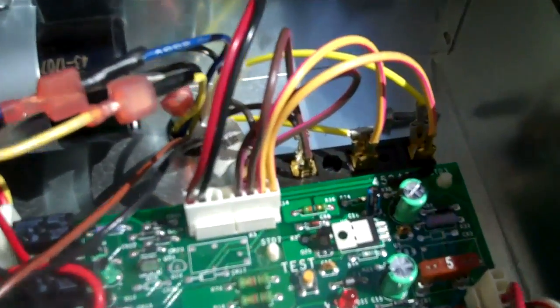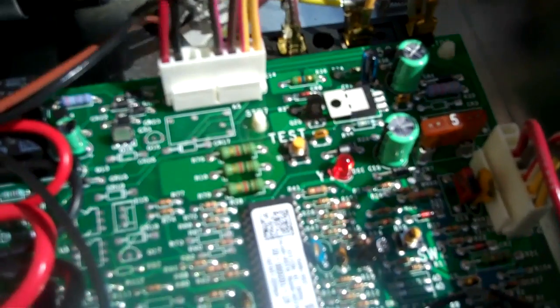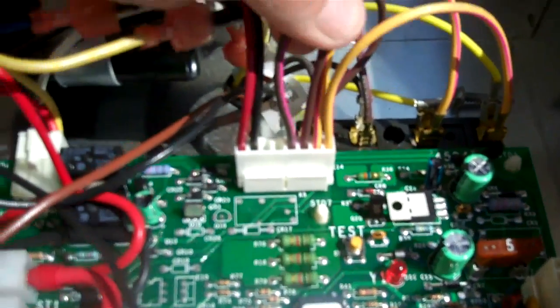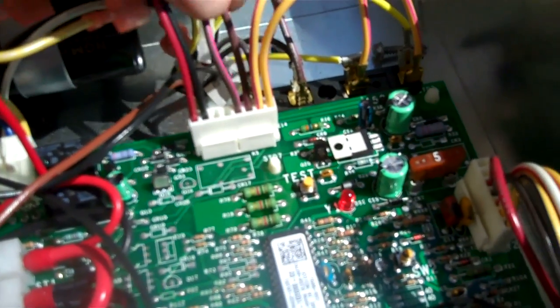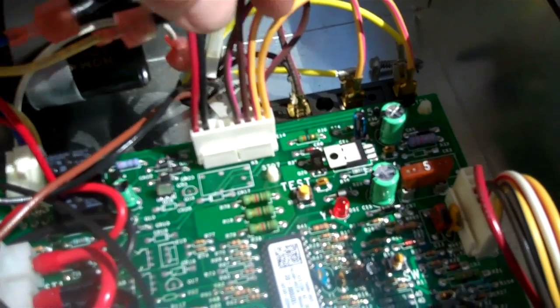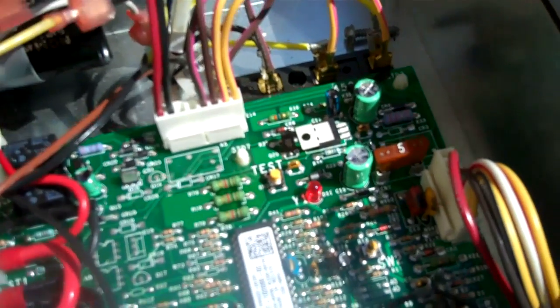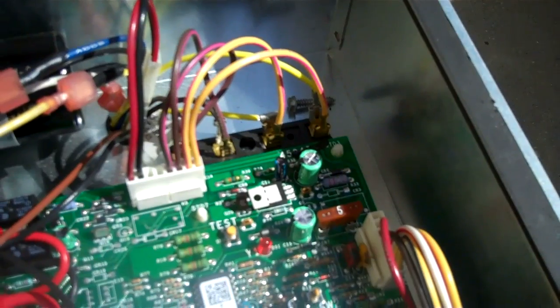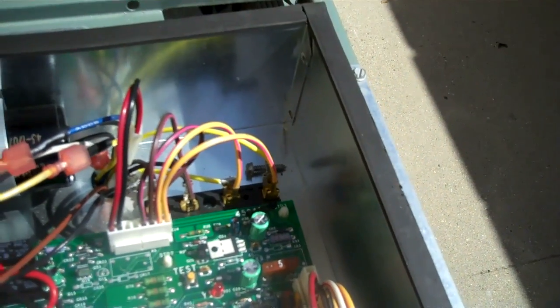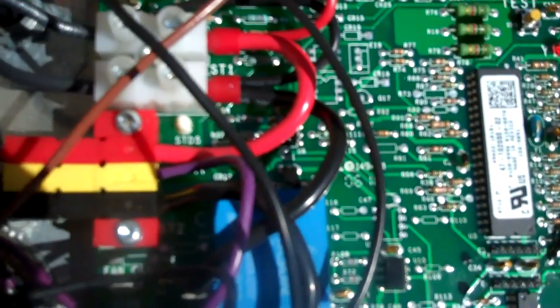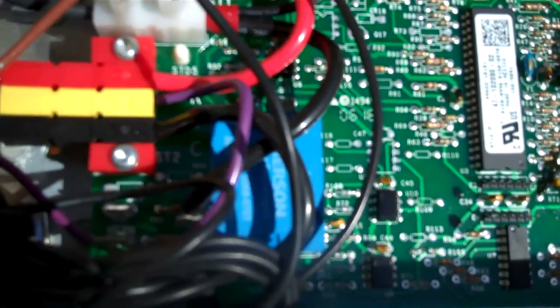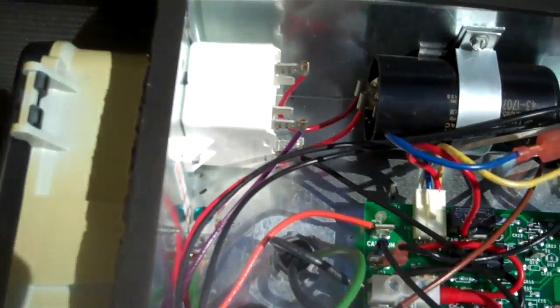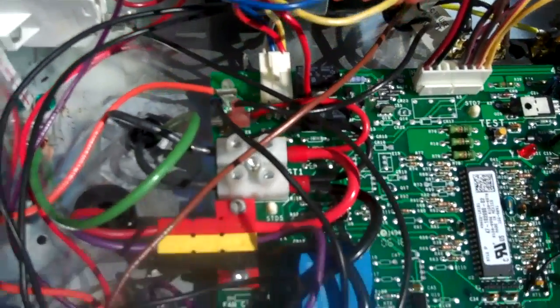So that comes up to here, and then, so that's the plug. This one here is low pressure cutout. This here is high pressure cutout. If you ever have a problem, you can just jumper right over with your alligator clips over in the corner there. Your high voltage is coming in here. This is the plug for the compressor. There's your capacitor, run capacitor, start relay, start capacitor.